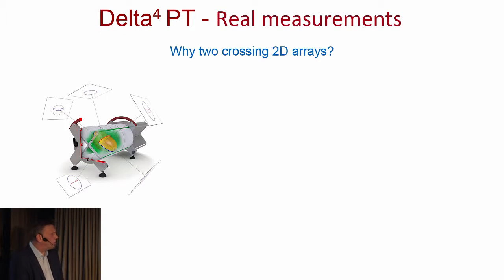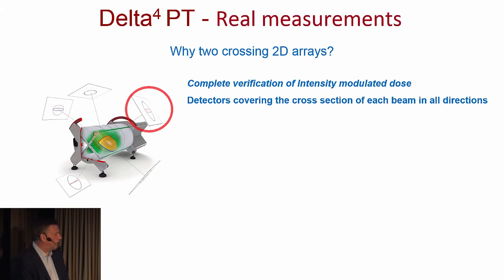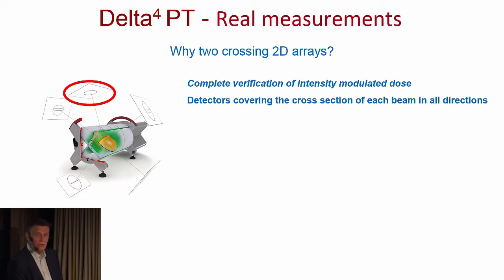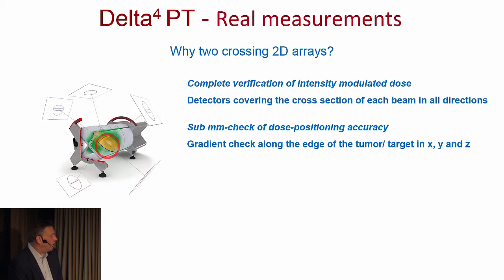Why are we using two crossing 2D arrays in the Delta4 system? And why did we spend the effort to actually patent that? Well, it's a complete verification of intensity modulated dose. The detectors cover the cross-section of each beam in all directions, as you see here on the graph. It gives you a sub-millimeter check of the dose position accuracy and the gradient check along the edge of the tumor slash target in X, Y, and Z.